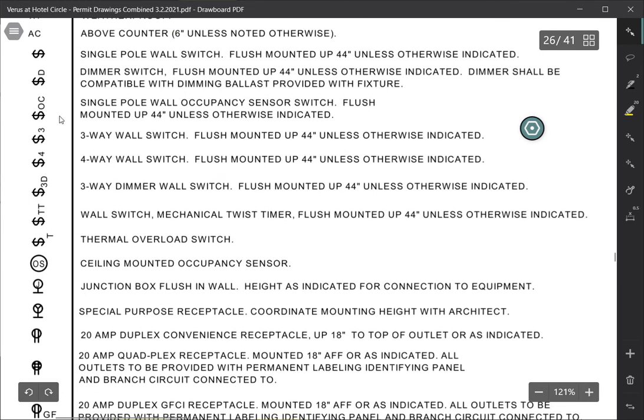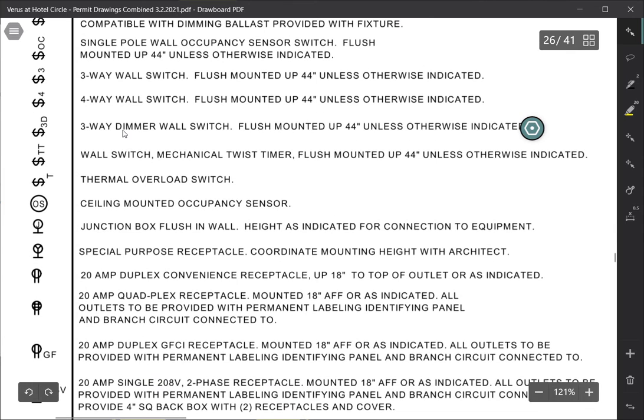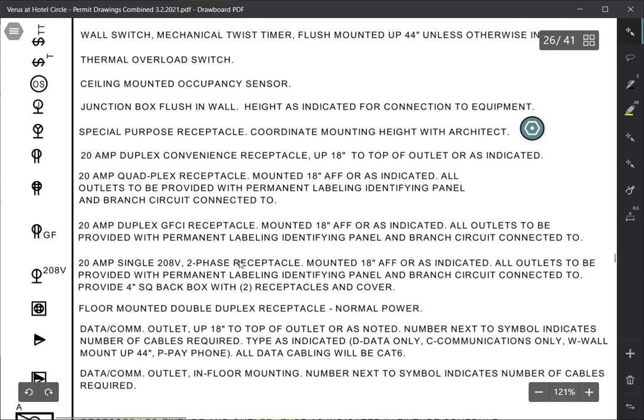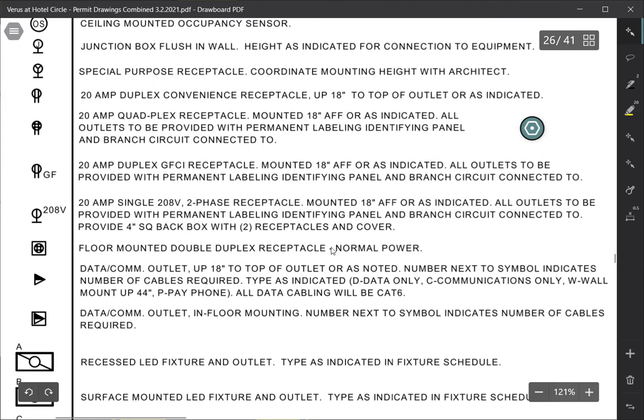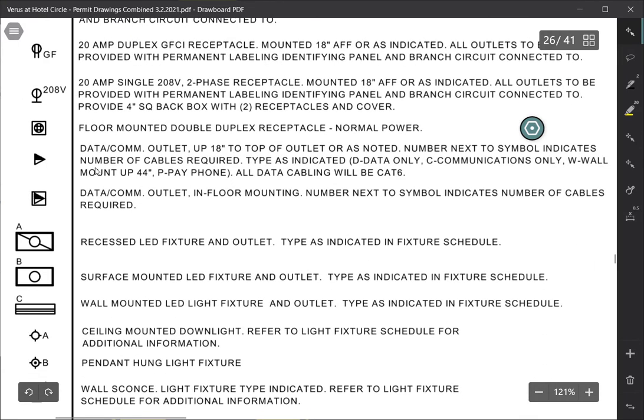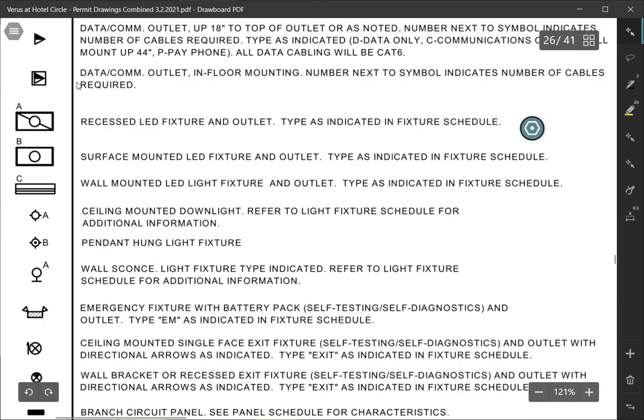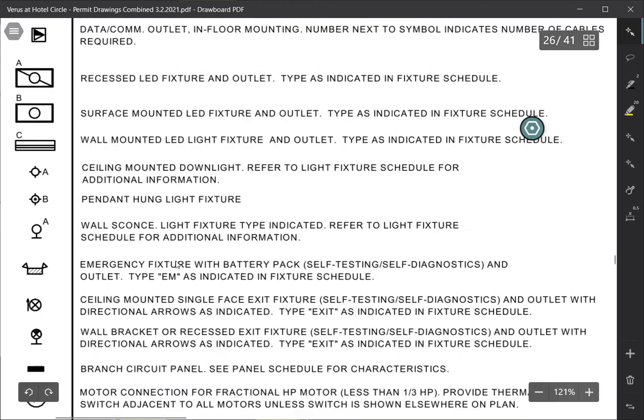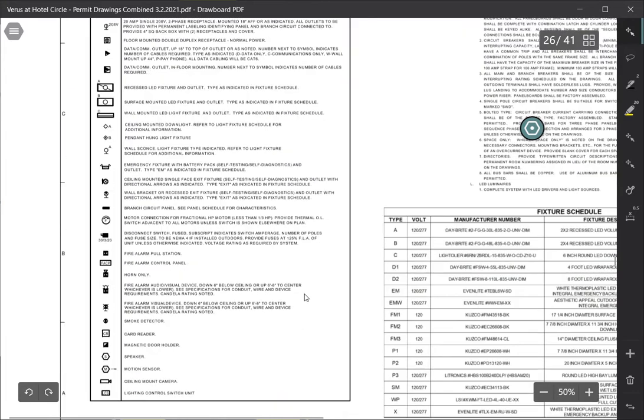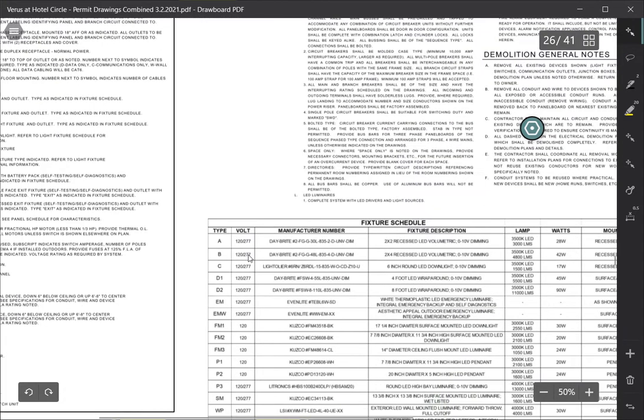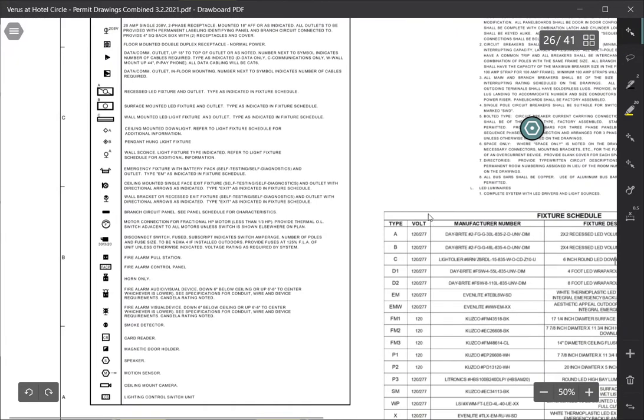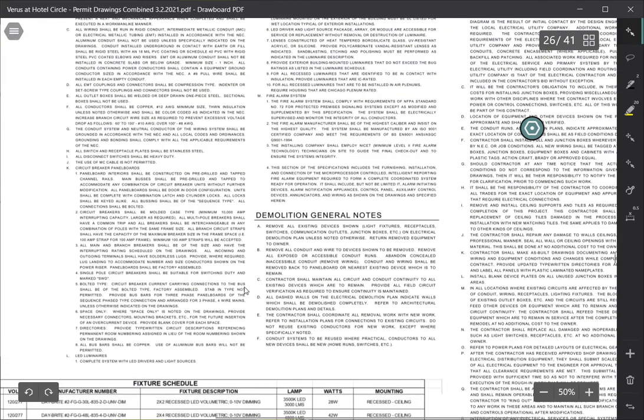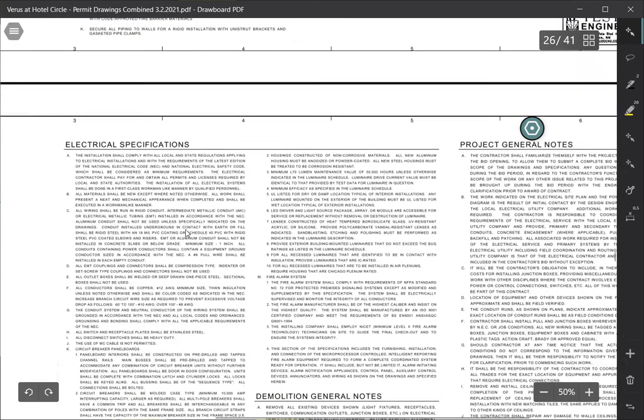And then it will go all the way down. This is a single pole occupancy sensor. They make three-ways, so it's good to know. This is a three-way wall switch, three-way wall dimmer, so this kind of breaks it up so you can see. This is an occupancy sensor, a thermal overload switch, a quad receptacle, a regular receptacle. Once again, 18 inches is going to be the typical height unless it is specifically noted somewhere on the plans that it needs to be a different height. Floor mounted duplex receptacle, datacom, recessed lighting, surface mount, all that good stuff. So you can go down this entire list and you'll see something, and if you have any questions you can always refer back to this first page. The engineer or whoever drew the plans should have put everything that you're going to need to find on that particular list.